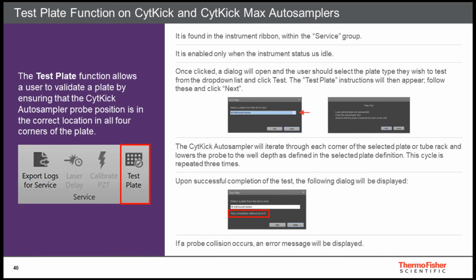For systems with CytKick, the test plate function can be used to check that the dimensions of the plate entered in the software are appropriate. The system runs through a quick probe calibration with the specific plate in place to ensure accuracy of the plate dimensions. Again, the software is quite descriptive and will walk you through the process once the test plate script is initiated. If all works well, a "Test complete without error" message should appear in the window.